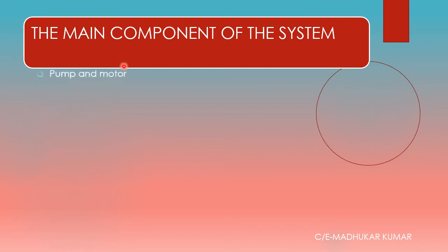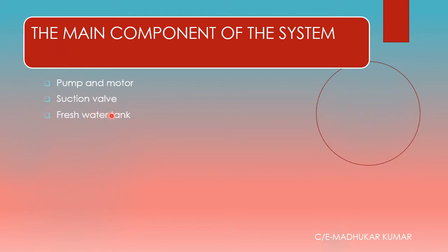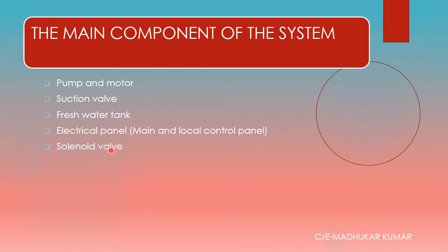The main components of the hypermist system include the pump and motor, suction valve, fresh water tank, and electrical main and local control panels. The local panel is generally in the steering compartment, the pump installation and activation system are in the fire control station, and repeater panels are in the bridge and engine control room. Each individual zone is attached with a solenoid valve.